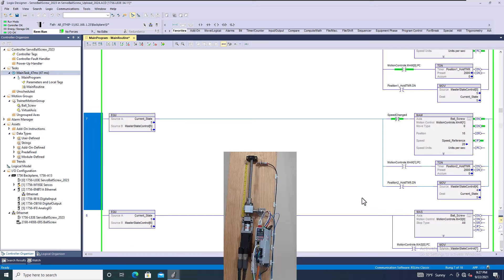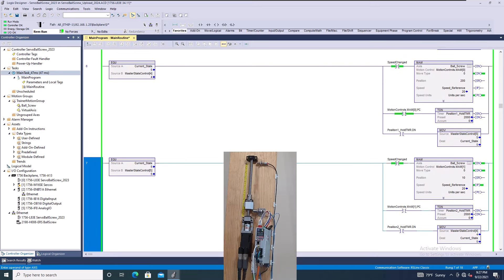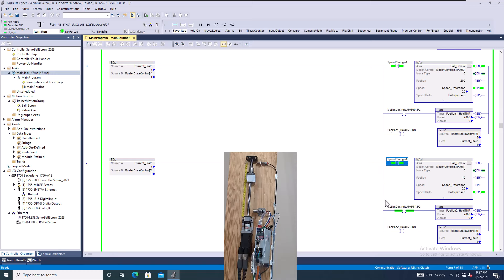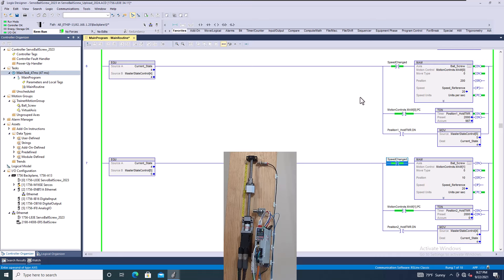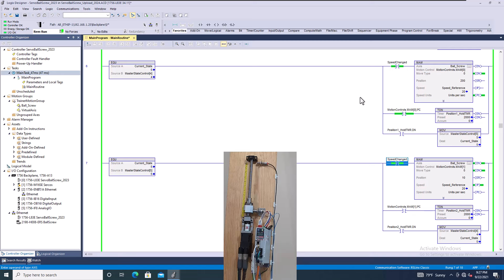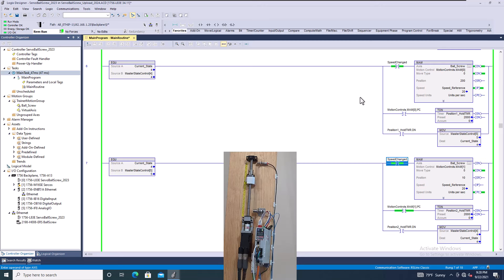I'm going to take this double instruction out that I placed in there because there's zero reasons why you need to have that. Unless you can somehow convince me that you have an absolute reason. I've seen this exact process happen time after time, or even the person would have a duplicate and have it AFI'd. They said we had to have it because of the version of Control Logix we're running. I've never seen a tech note say that. I've talked to many servo control experts with Rockwell, and we actually took that out and it worked perfectly fine.